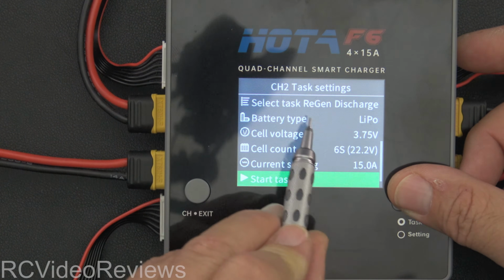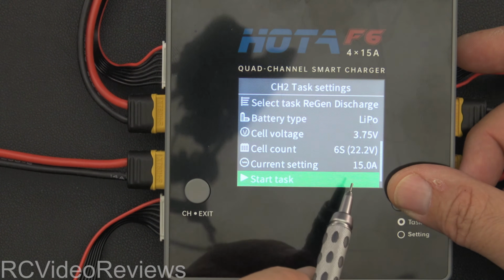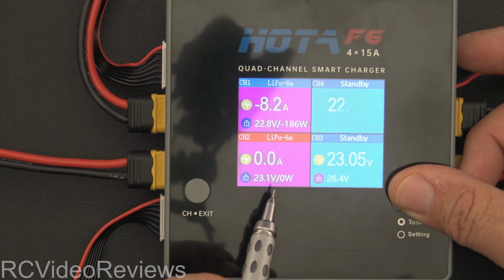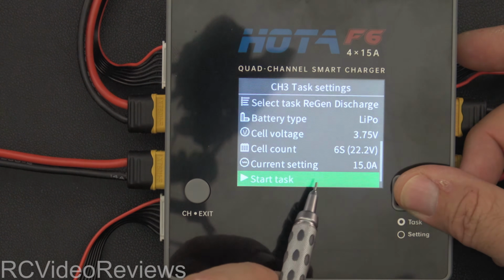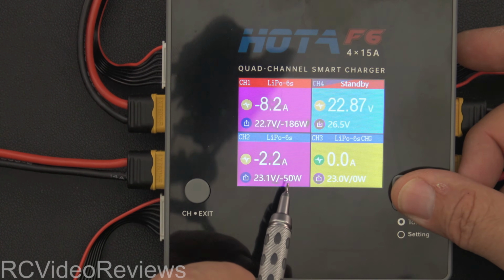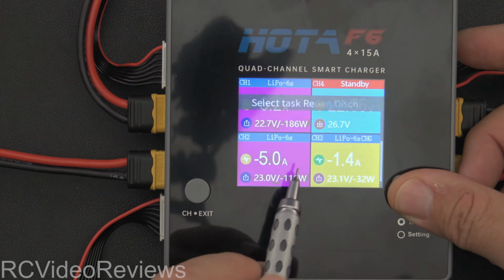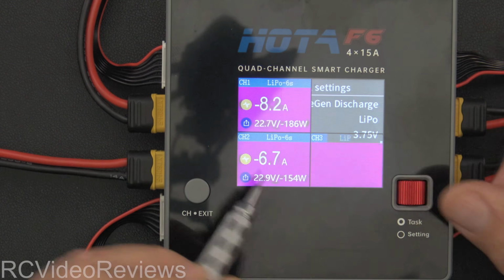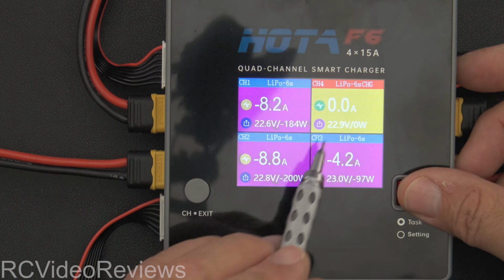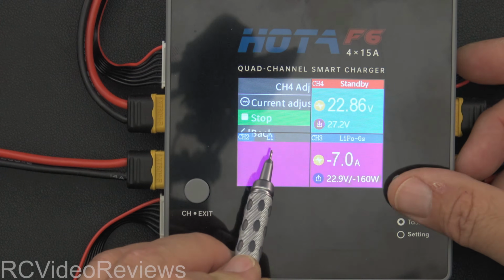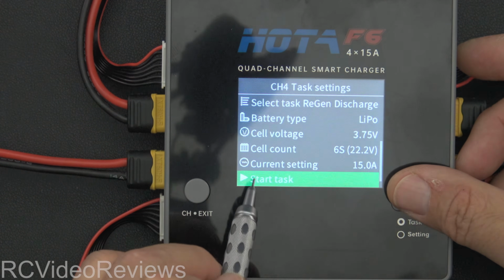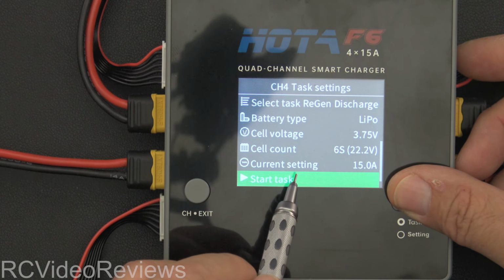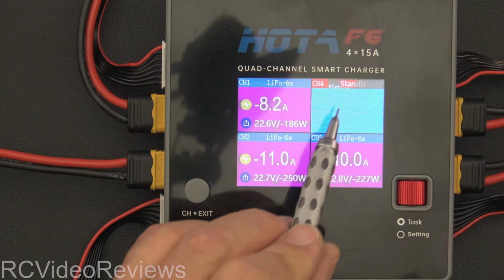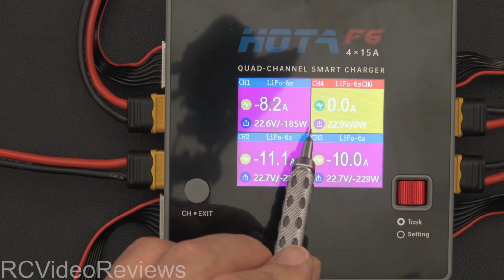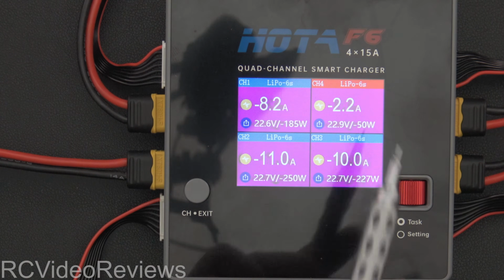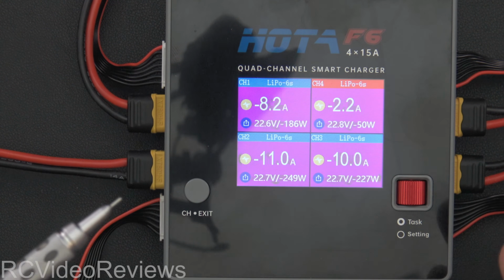We're going to start up channel 2. Remember, it remembers the last thing you did. So there's the regen discharge at 15 amps. We'll hit start there, and then we'll go to channel 3 and hit start, and then channel 4. There's the skip, and then we'll hit start. So now we've got all 4 channels. Wait, hey, hold on a minute. You are supposed to be discharging. Regen discharge down to 3.75. Okay. I wonder why that went yellow. It should go purple. We'll let it, there it goes. It turned purple. Maybe I just got too fast.